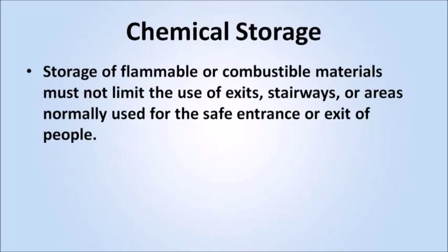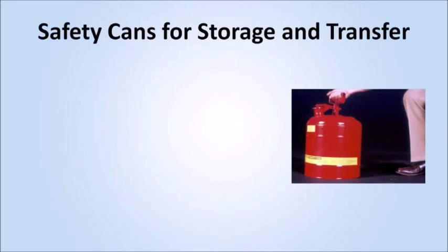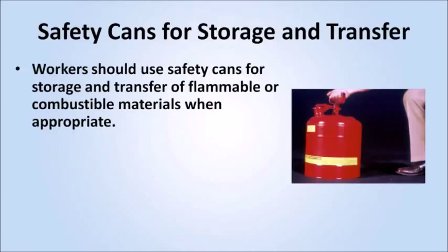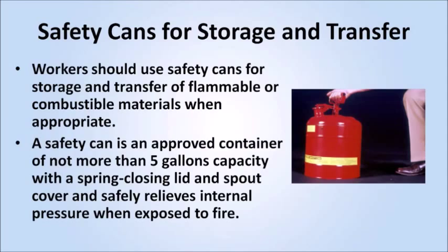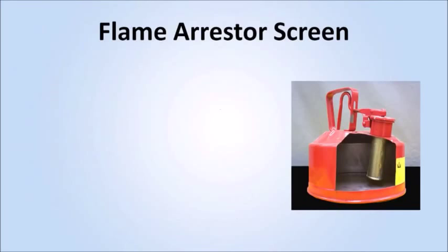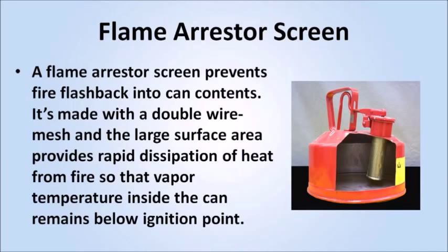Storage of flammable or combustible materials must not limit the use of exits, stairways, or areas normally used for the safe entrance or exit of people. Workers should use safety cans for storage and transfer of flammable or combustible materials when appropriate. A safety can is an approved container of not more than 5 gallons capacity with a spring closing lid and spout cover, and safely relieves internal pressure when exposed to fire. A flame arrestor screen prevents fire flashback into can contents. It's made with a double wire mesh, and the large surface area provides rapid dissipation of heat from fire, so that vapor temperature inside the can remains below ignition point.